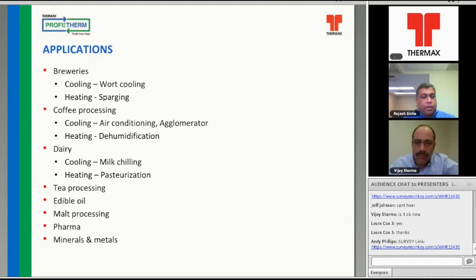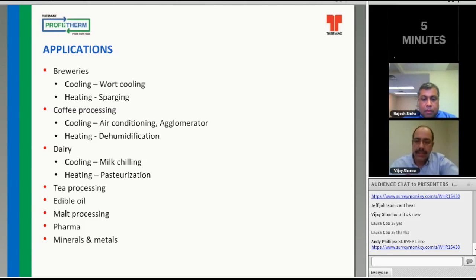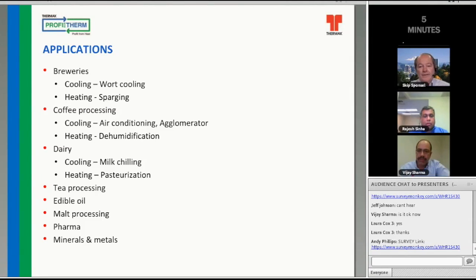Thanks, everyone. Going forward, what Rajesh has been telling about the various products of chiller heater, high-efficiency chiller heater. This is an extended understanding of where all these absorbers are being used industry-wise, to start with breweries, which is used typically for cooling requirement in the wort process, and heating, which is again a sparging process used in breweries. Coffee processing also uses cooling requirement, and heating and dehumidification. Dairy is again one of the challenging applications that we have been doing, because the primary reason is the absorber is giving you a chill water of 33.8 degrees Fahrenheit, which is among the lowest in the absorption technology. So dairy is again a sector that can use this. Tea processing, edible oil. So we just move ahead and see how the application has been used on various chiller applications with the temperature.